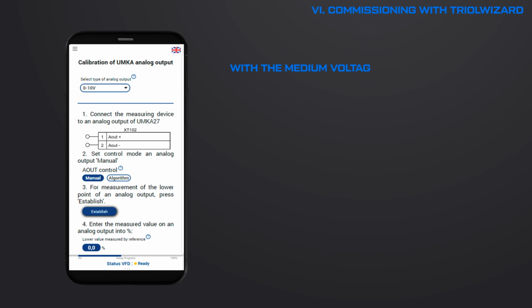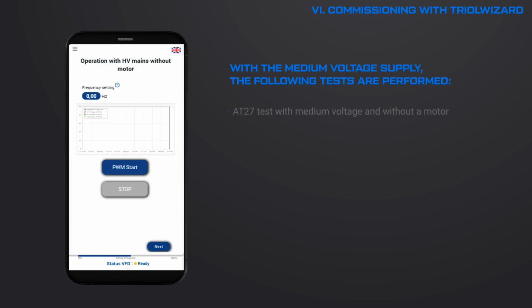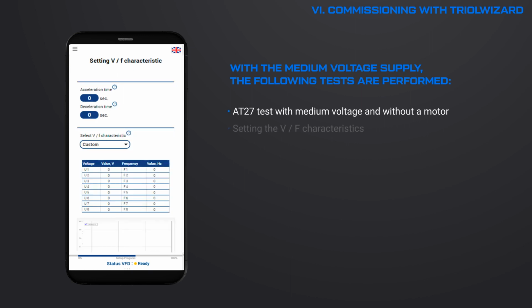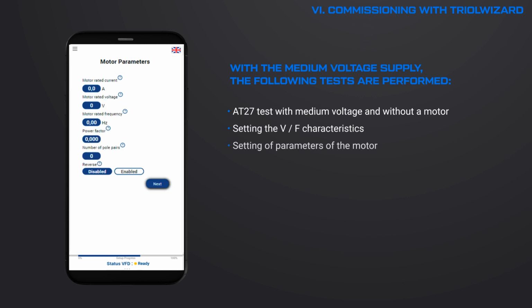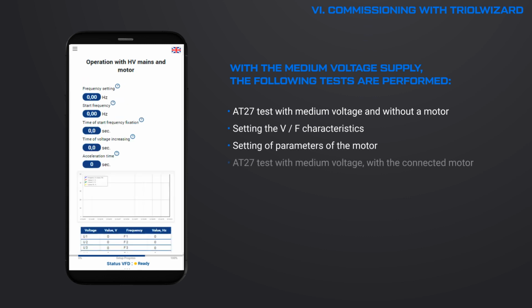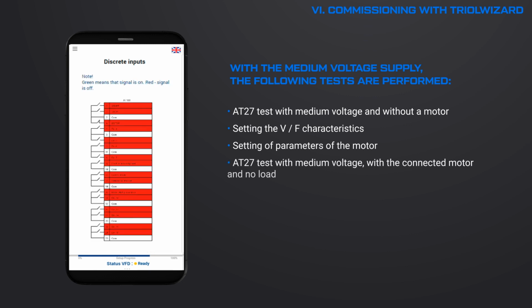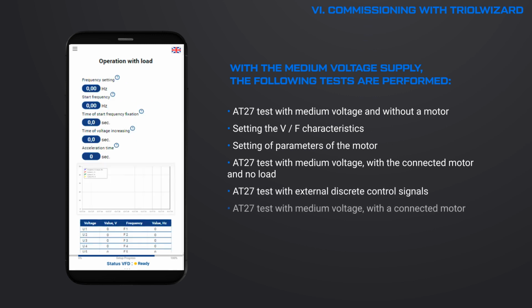With the medium voltage supply, the following tests are performed. AT27 test with medium voltage and without a motor. Setting the VF characteristics. Setting of parameters of the motor. AT27 test with medium voltage with a connected motor and no load. AT27 test with external discrete control signals. AT27 test with medium voltage with a connected motor and load.